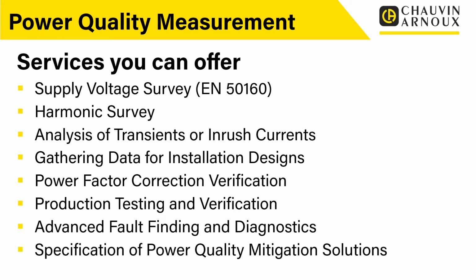Inrush currents, again, if you've got a particular piece of equipment where there are problems, where whenever we turn that motor on, it trips off that breaker, and sometimes we have to reset it 2 or 3 times and it'll finally be all right. Obviously, that isn't ideal. That's not how it's meant to be. So what you can do is actually do assessments of the inrush currents. You can measure what is going on, what's the increase, how long does it need to be there for, and then you can specify the correct characteristics of protective device.